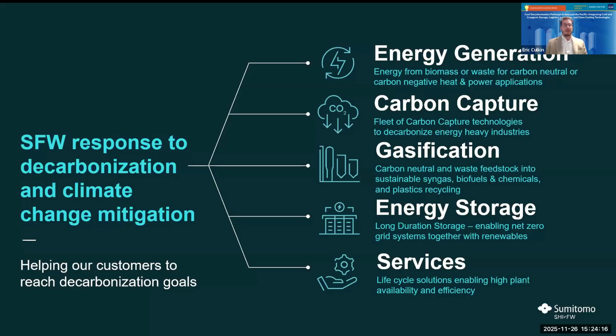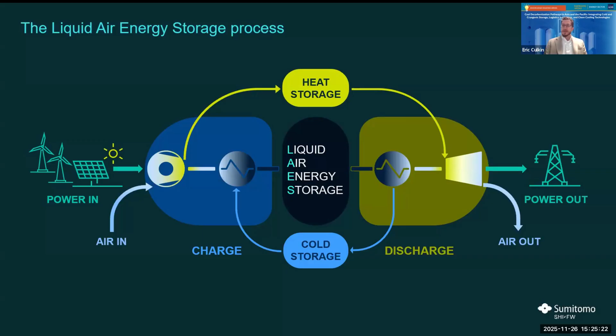Our long duration energy storage technology is liquefied air energy storage, built around the Claude process used in the air separation and LNG industries. Essentially, we use excess renewables to run compressors to compress ambient air, recovering the heat of compression and storing it, then liquefying the air to store in pressure vessels. That gives us high energy density and locational flexibility. When power needs to be dispatched back to the grid, we vaporize the air, recovering the cold energy of vaporization, then superheat the air and run it through what is essentially a steam turbine. It's built on well-established technologies from air separation, LNG, and traditional power generation, allowing for hundreds of megawatts of capacity at 8+ hours of storage duration.